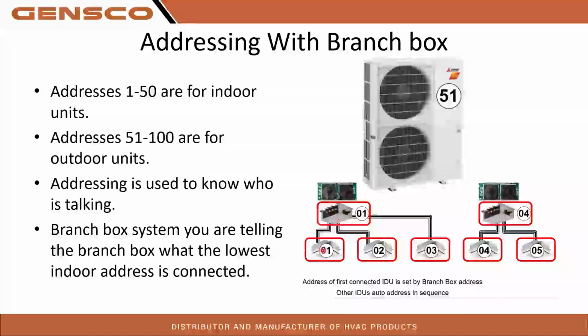So like this one to be address 1, because again, lowest address. Over here, if I got a 5-port, but I'm only using 3, but I want to keep those other 2 ports available, then I would take this address and make it address 6. That way we got 2 empty slots for when we do our future expansion. Because again, when you're addressing this branch box, your first one is looking for all equipment available until it sees this address here. So if it just sees 1, 2, 3, there's no more equipment, it says, okay, no more there, but the next address may be 6. Like, okay, now I know address 6 is on this one, continue on.